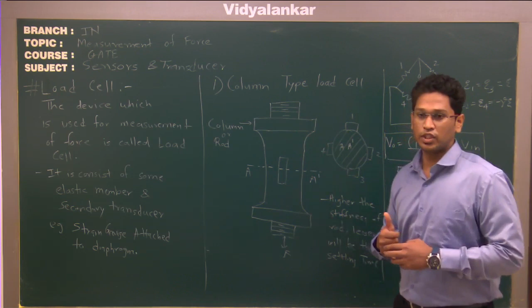Usually these strain gauges are connected in a full bridge configuration, and that is also Poisson's full bridge configuration. The meaning of it is, suppose epsilon 1 and epsilon 3 are the strains that are developed in strain gauge 1 and strain gauge 3, then the strain which is developed in strain gauge 2 and strain gauge 4 is minus mu times epsilon. That means minus Poisson's ratio times the strain which is developed in strain gauges 1 and 3. This type of configuration is called Poisson's full bridge configuration.